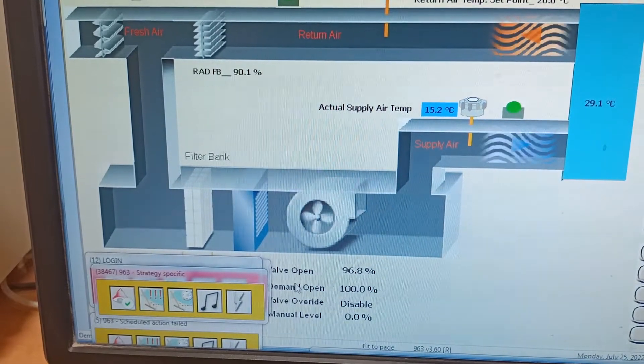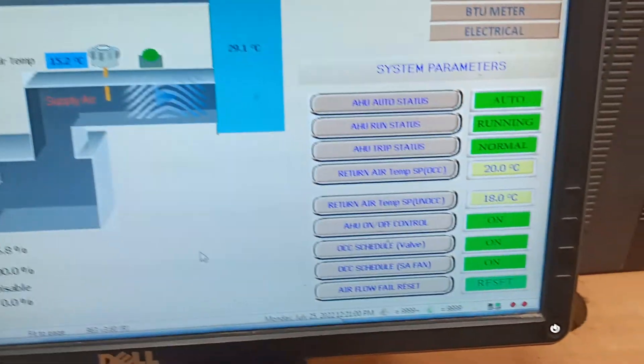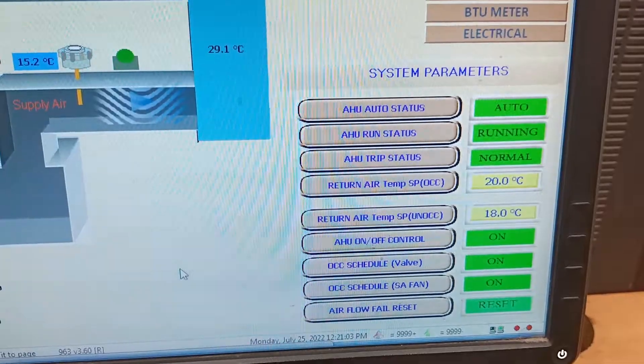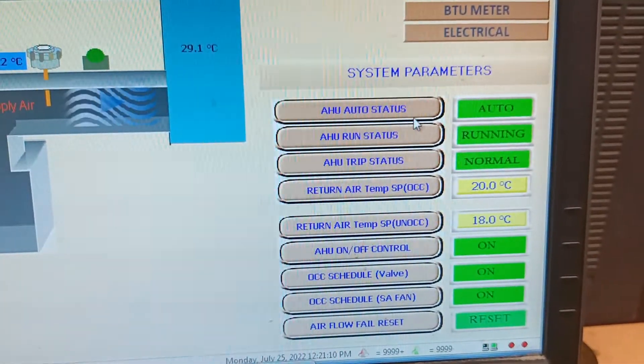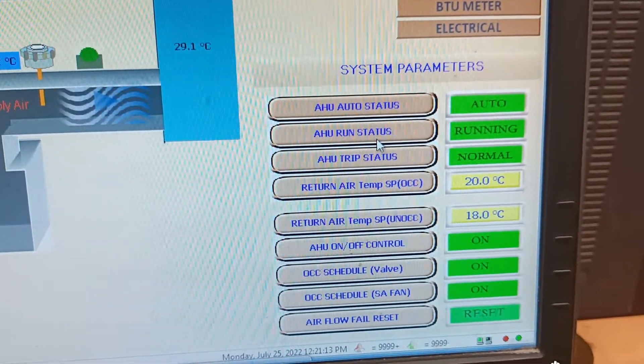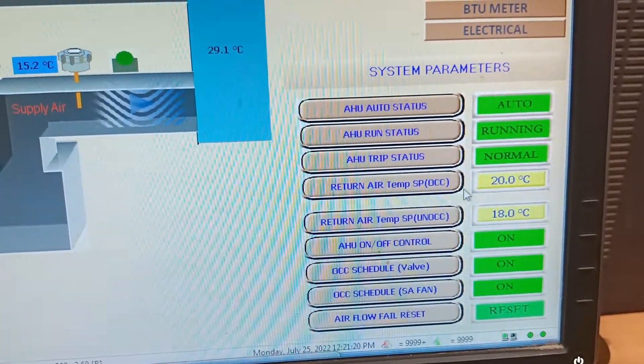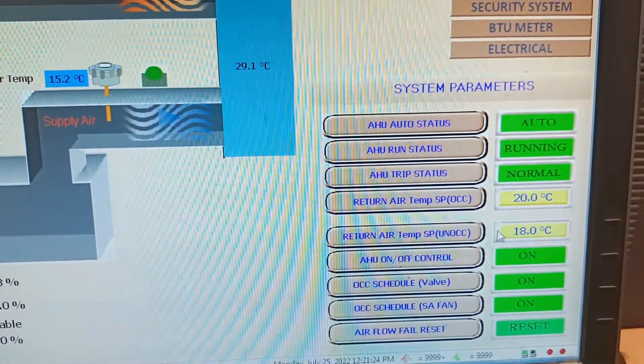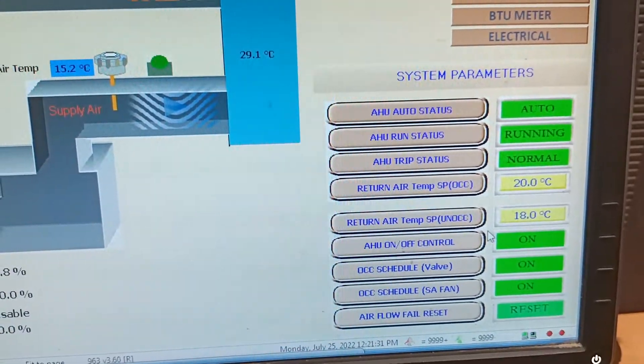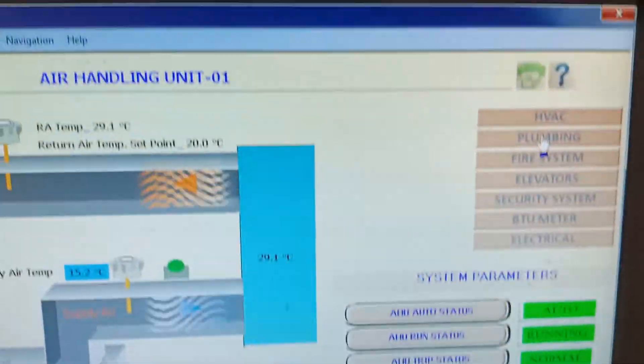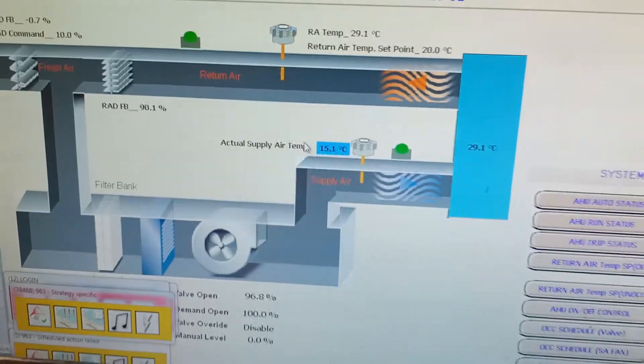Here you can see the fan is rotating and it's working — the demand open means the valve is open 100%. Under system parameters you can see the status: AHU auto status is working on auto, AHU run status means it is in running condition, and AHU trip status means if it gets a trip it will show normal. The temperature in degree Celsius is showing return air temperature at 18 degrees. This is the status for AHU on/off control, and all these are interfaced with the system.